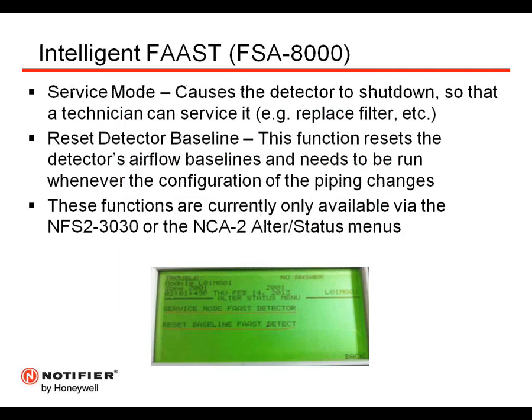With the NFS2-3030, you can also put the detector into a service mode from the panel, which will cause the detector to shut down. So if a technician needs to go out there to replace a filter or do some other type of service on the Intelligent FAAST unit, they can put it into service mode through the NFS2-3030. Through the NFS2-3030, they can also reset the detector baseline. This function resets the detector's airflow baselines, and it would need to be run whenever the configuration of the piping changes. So if someone needed to add some additional pipes to the network, they would go into the NFS2-3030 or the NCA2 and reset that detector baseline.